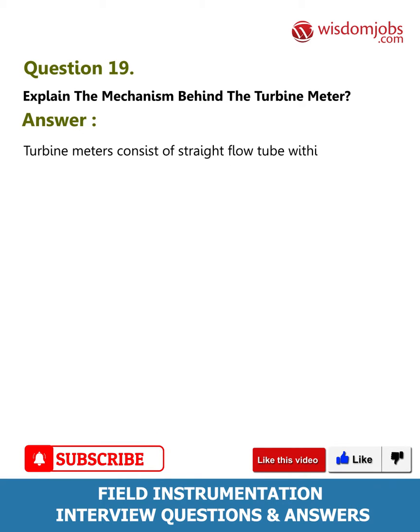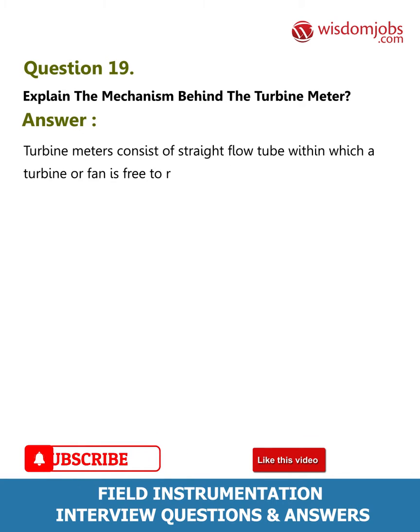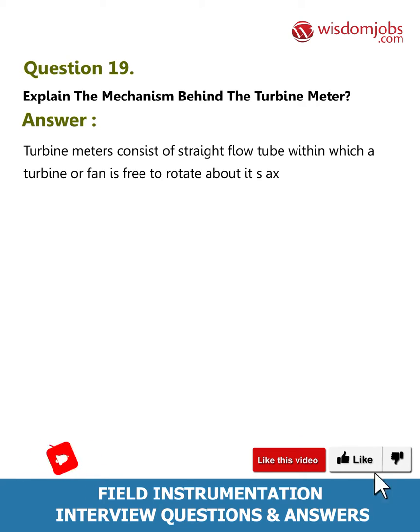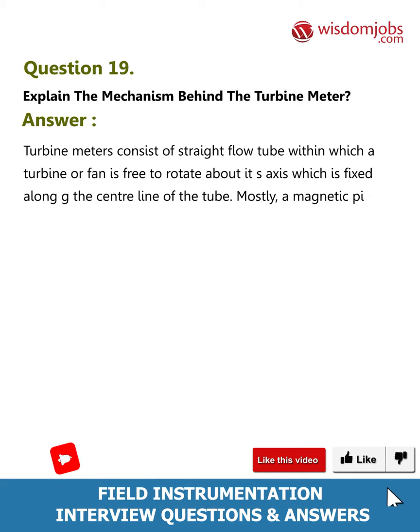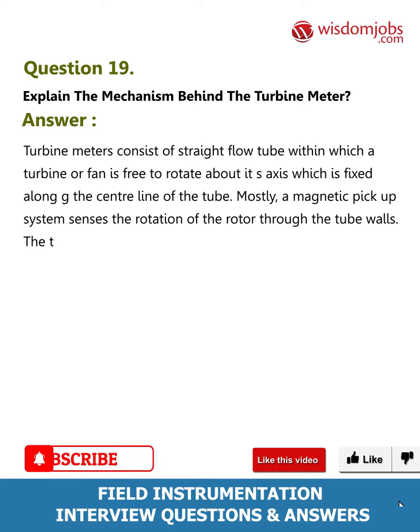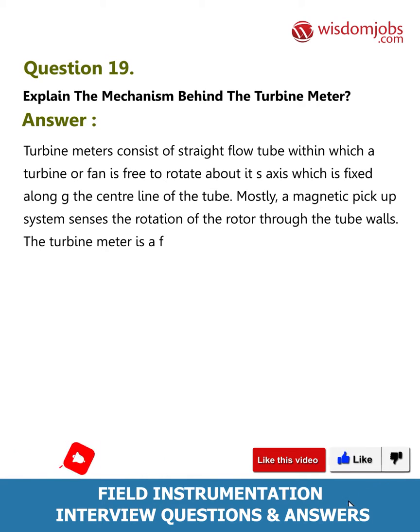Question 19: Explain the mechanism behind the turbine meter. Answer: Turbine meters consist of a straight flow tube within which a turbine or fan is free to rotate about its axis, which is fixed along the centerline of the tube. Mostly a magnetic pickup system senses the rotation of the rotor through the tube walls.